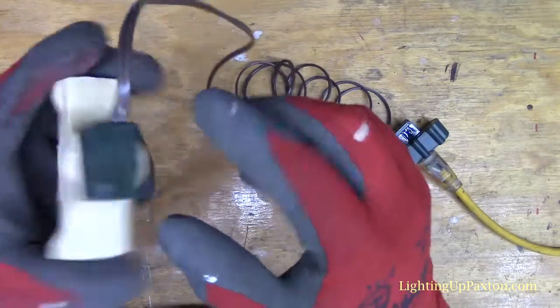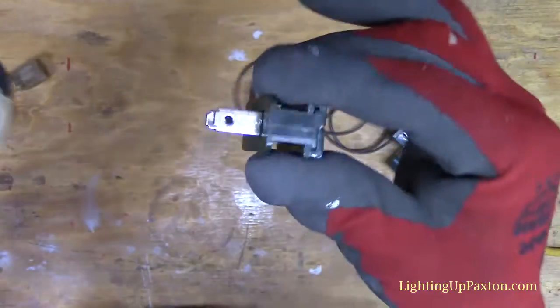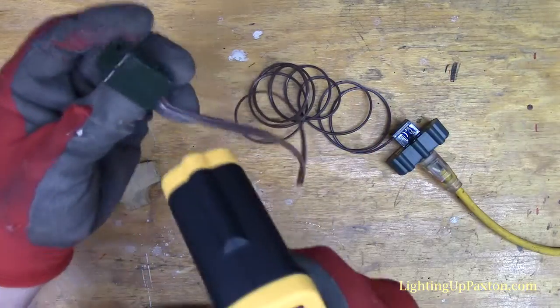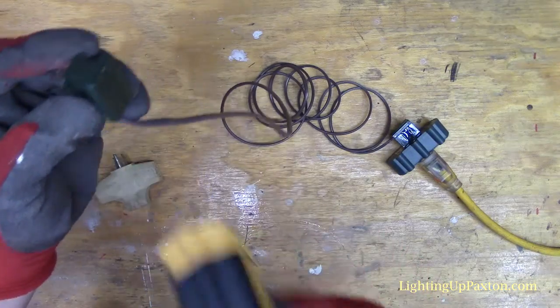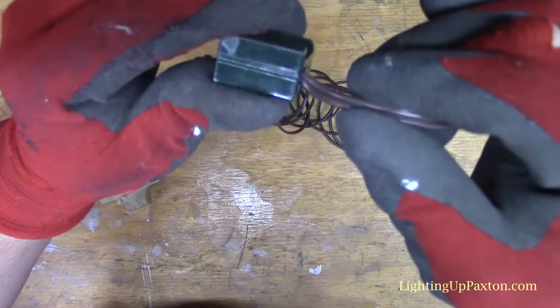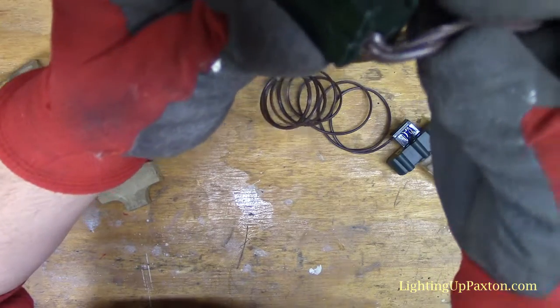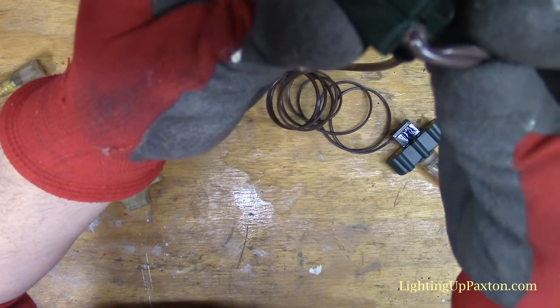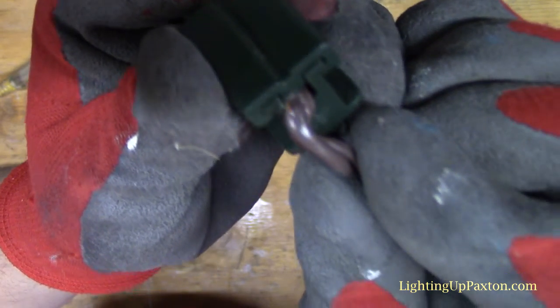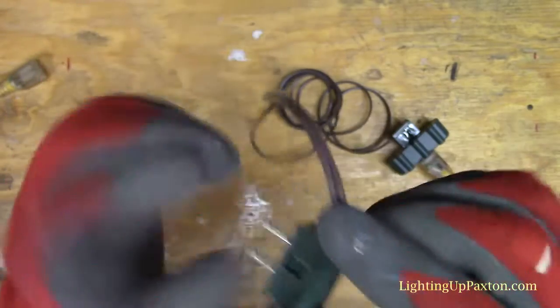Okay, gloves are on so I can touch it. Here's our male plug. Let's get a temperature reading on the male plug - looks to be right around the 150 range. But I mean, look at this. That wire has melted and it started to - look at that - the insulation jacket is totally melted off right there. See the bare wire right there? It's totally melted.